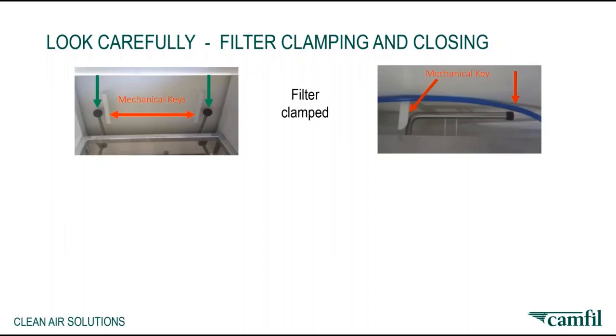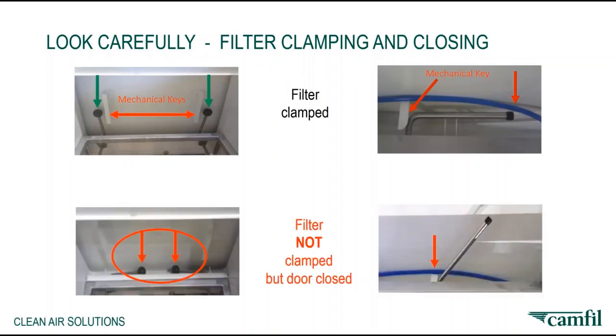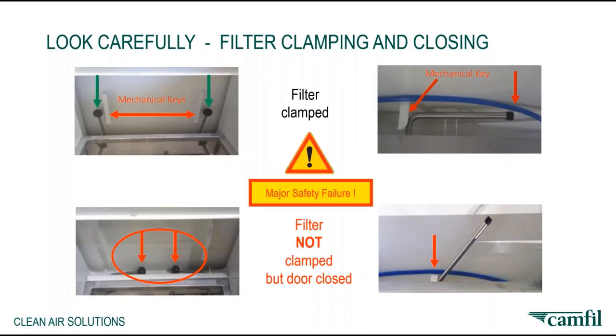After insertion, well, there's still clamping, and then you want to close the housing. That should also be fail-safe. Here we see 2 examples of filter clamping in the closed position, and if you look closely, they both do have mechanical keys to ensure fail-safe operation. But if we look in the closed position, closed on the left, partially closed on the right, it still was possible to close the door, and from the outside, everything seems all right. And inside, we're having trouble. This again has to be considered a major safety failure.